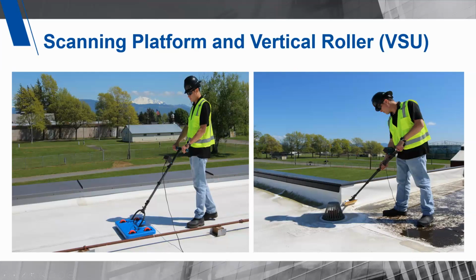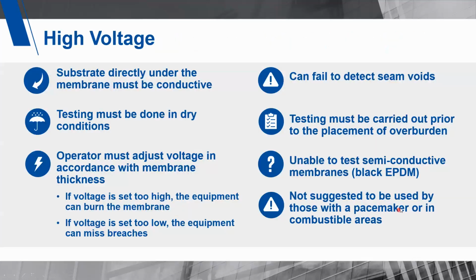High voltage, on the other hand, the equipment manufacturer suggests it should not be used by someone with a pacemaker. You should not use this method in a combustible area. There is an actual spark. It's high voltage but low amperage, so I don't think it can really kill anybody, but you don't want to touch that spark. It does hurt.